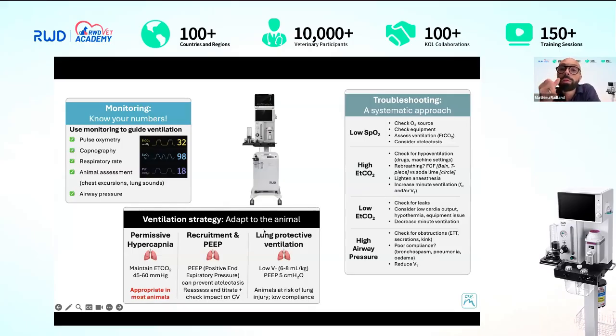In terms of troubleshooting, what's really important is to use a systematic approach. So when you have low saturation, which is not so common, check the oxygen source, check the equipment, and check that the animal is actually ventilated. If you have high end tidal CO2, check for hypoventilation. What can cause that? Resistance, drugs, all of it together. Is there anything you can do to make the animal's life a little bit easier? Try and reduce anesthetic depth. See if you can use lighter weight equipment and less resistance.